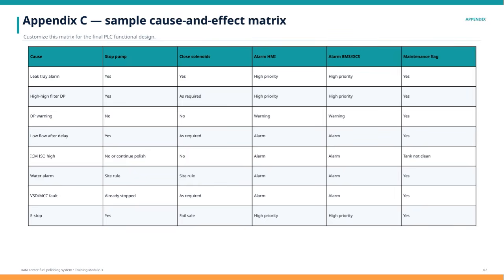Similarly, a high filter differential pressure will prompt similar responses, indicating the criticality of these conditions. Other conditions like a low flow after delay result in stopping the pump and possibly closing solenoids, along with alarms and maintenance notifications. Some faults, like the VSD or MCC fault, are handled by ensuring the pump has already stopped, with solenoids closing as required. This matrix helps ensure safety and proper maintenance by defining clear, prioritized responses to various system alarms and warnings. You can adapt this template to meet the specific requirements of your system and facilitate effective operational control and monitoring.